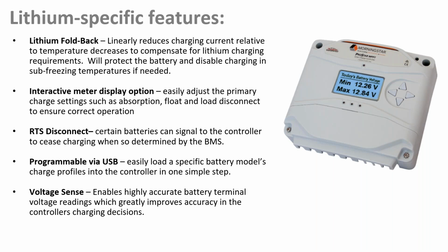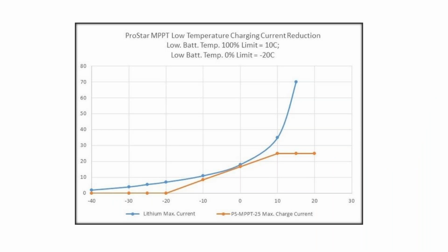What voltage sense does is give our products the ability to get a very accurate voltage sense, so that small minor changes in battery voltage impacting state of charge and system functionality are measured with good visibility. We accomplish this with a secondary sense line connected to the battery posts, and those wires go around a lot of the bus bars, breakers, disconnects and interconnection hardware that over time can introduce voltage drops. So we get a really clear picture of the voltage right at the battery posts, bringing much better charging accuracy.